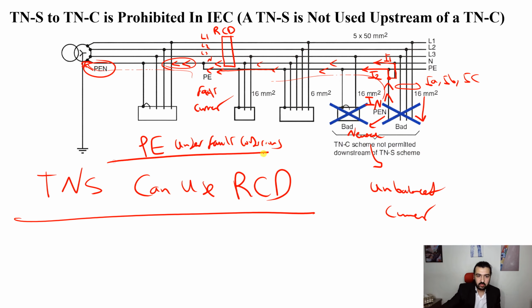This is very important because you will find that when current passes through it, it will cause some issues which we are gonna see. Okay, so the first problem here is that IN should be I1 plus I2, right? However, only I1 gets back through the RCD. I2 goes down away from the RCD. The RCD does not see this. So the RCD senses this I1 missing I2. So I2 means that there is a problem in the system or there is a leakage current. So the RCD will operate because the neutral is not I1 plus I2. It is only I1, so there is a missing current. So the RCD will operate if TNC is ahead of TNS. This is the first problem.